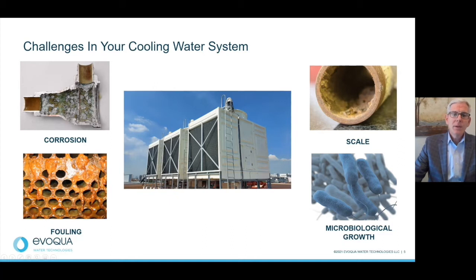The cooling tower pictured in the center of this slide is what allows the transfer of heat from the server room to the atmosphere. This process is commonly referred to as evaporative cooling, which in its own right is a sustainable process. The water that has absorbed the heat from the servers enters at the top of the cooling tower, and it falls to the bottom as air is circulated across the water, allowing a portion of the water to evaporate. This releases the heat into the atmosphere.